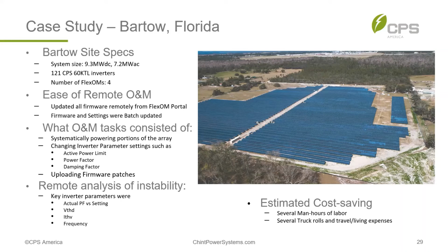Even though CPS was able to remedy the issue in about 3 days, you can imagine this would have taken significantly more time to accomplish the troubleshooting phase without the ability to instantly change settings across the entire fleet of inverters remotely. The perturb and observe duty cycle was too long to even be effective - you may miss the observation during the time consumed trying to make the setting change manually.